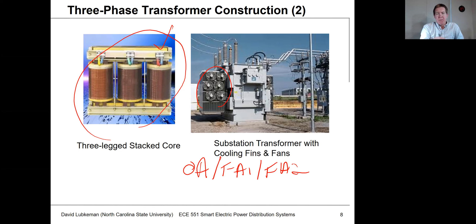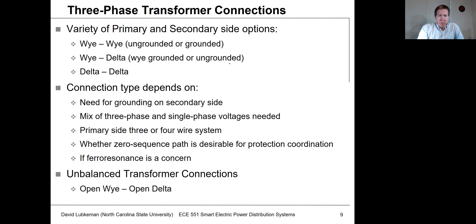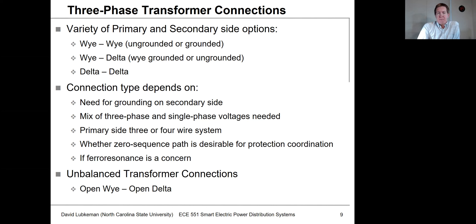This unitized three-phase transformer is very common in substations and for large industrial loads. As far as three-phase transformer connections are concerned, we have a variety of primary and secondary options. Remember, primary is the medium voltage side and secondary is the low voltage side connected to the customer. We could have Y-Y (grounded or ungrounded on either side), Y-delta, delta-Y, or delta-delta connections, with various reasons for choosing one over another.